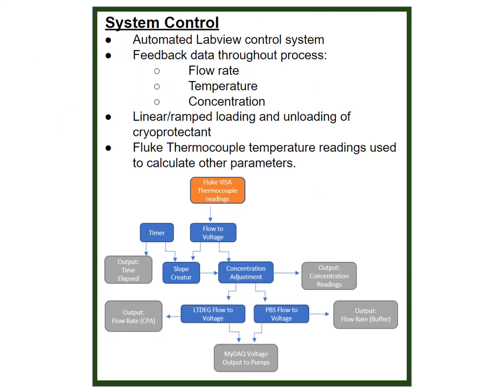Here's the overview of our control system for the entire process. It needs to be an automated LabVIEW system, with the main feedback points being flow rate, temperature, and concentration. It requires a linear and ramped loading and unloading of the cryoprotectant. As shown in the block diagram at the bottom, the Fluke VISA thermocouple readings drive the other calculations for the rest of the parameters.